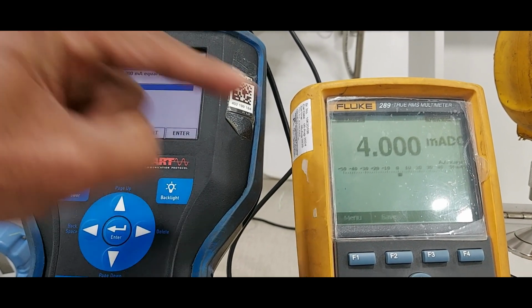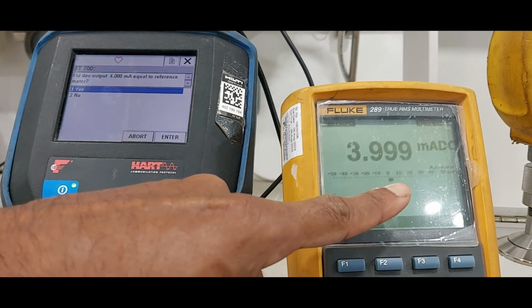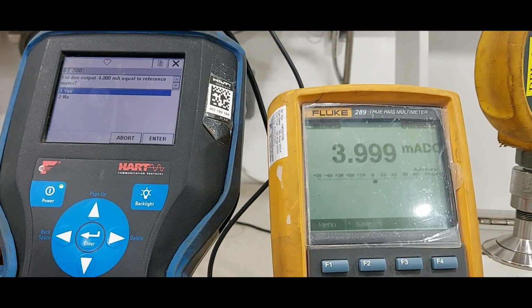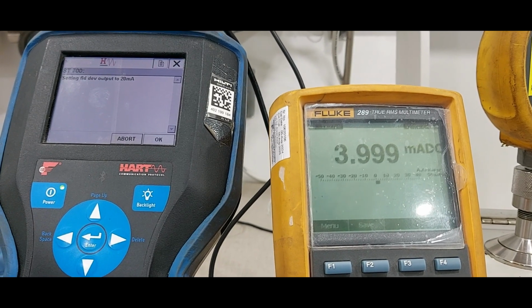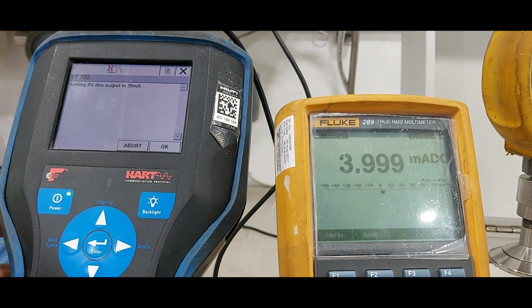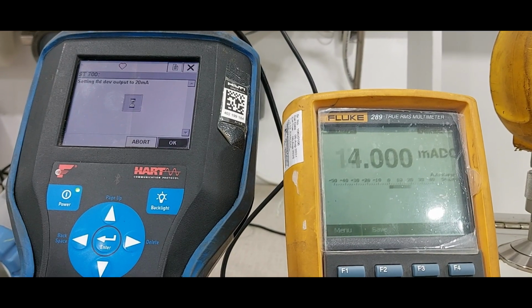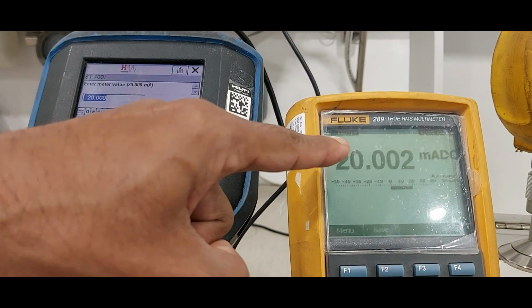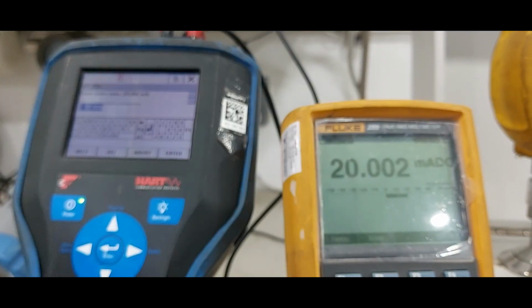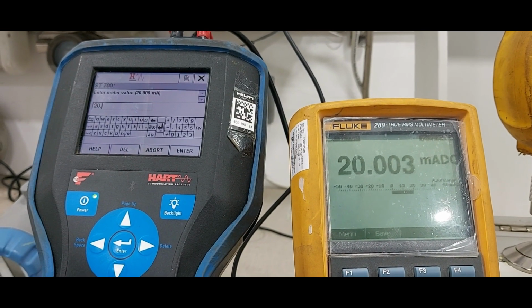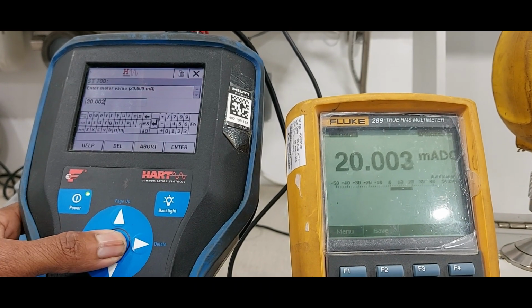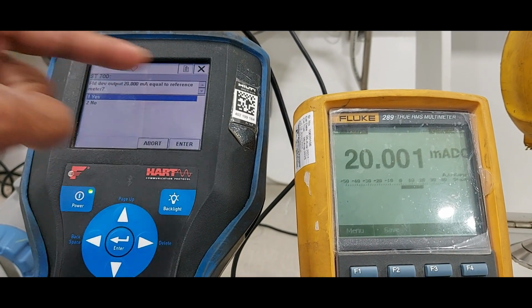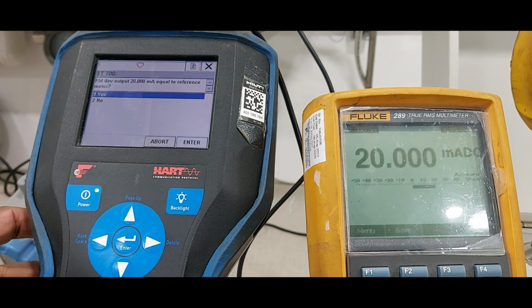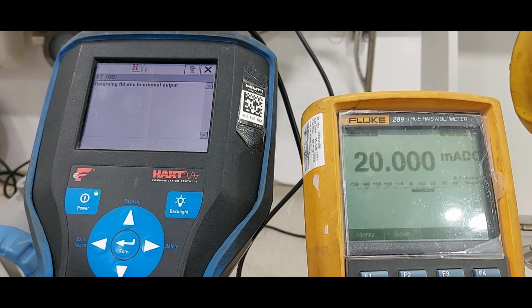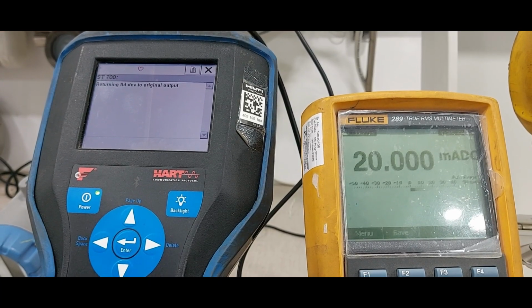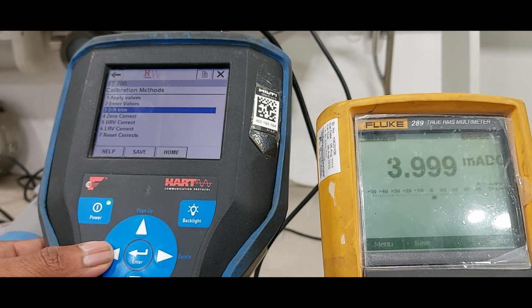Check the field reference value equal to output value. That is both are same. Then press OK. Next is setting the field value at 20 milliamps. Then OK. Output is showing 20.002. Then OK. Equal to reference meter, both are same. Then OK. Retain the original output value. Press OK.